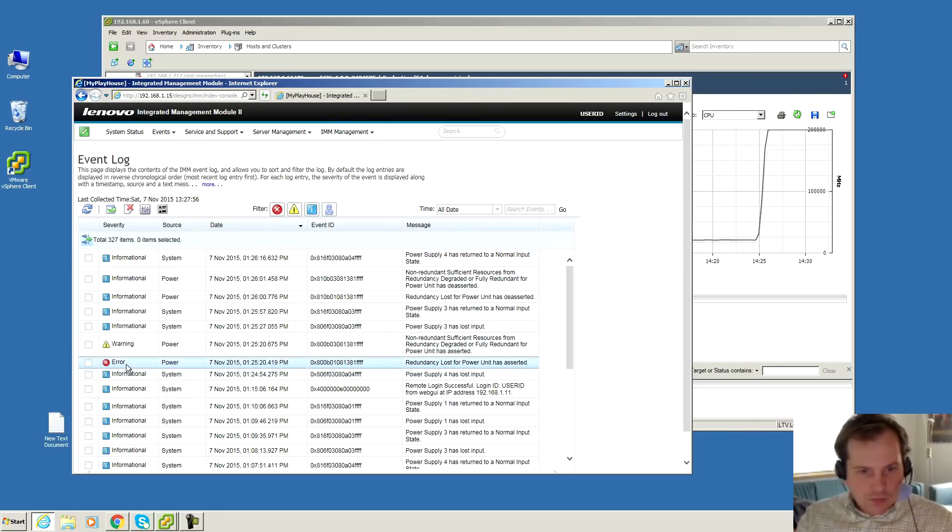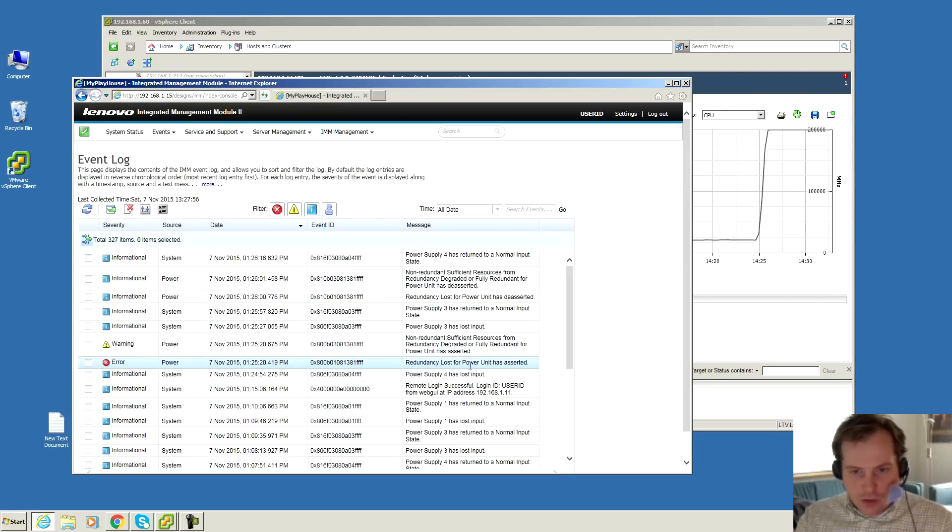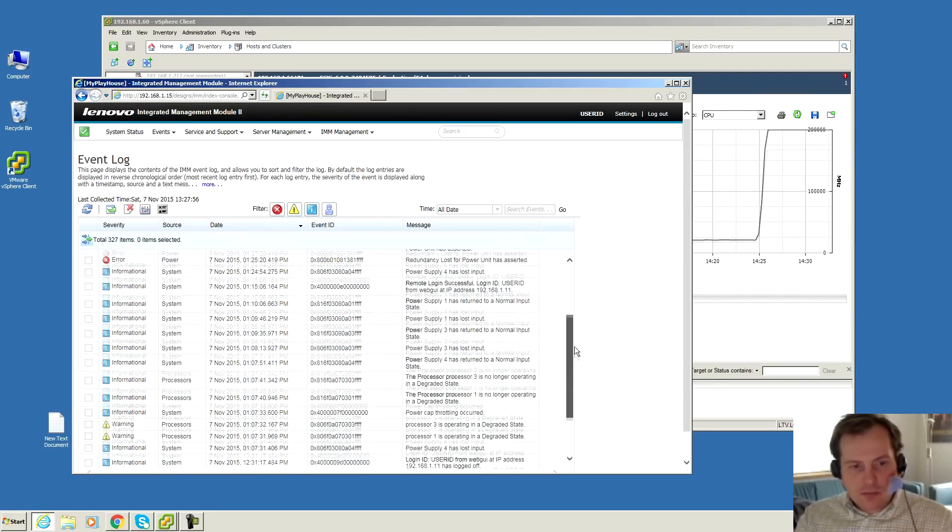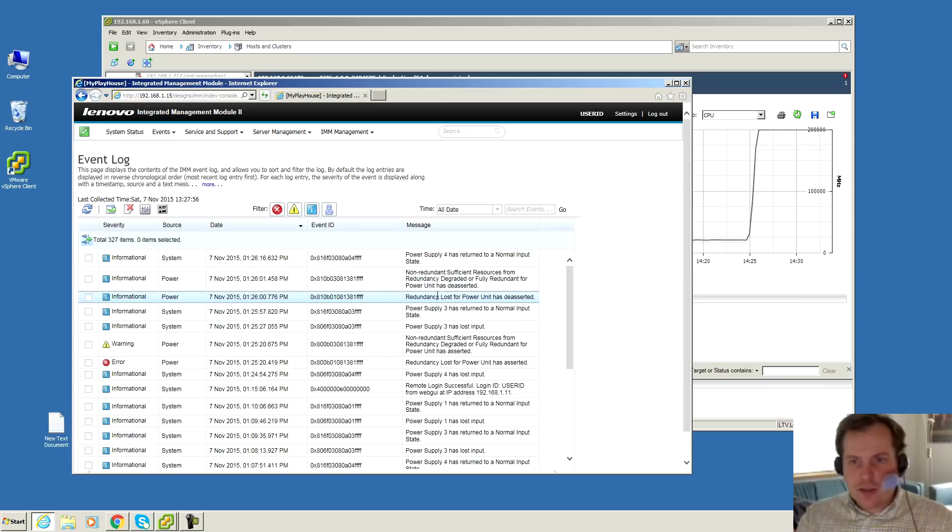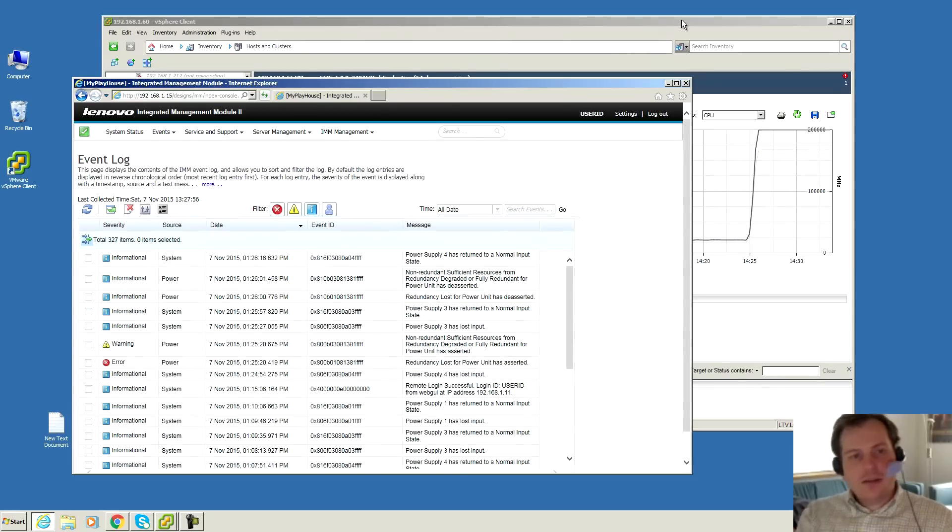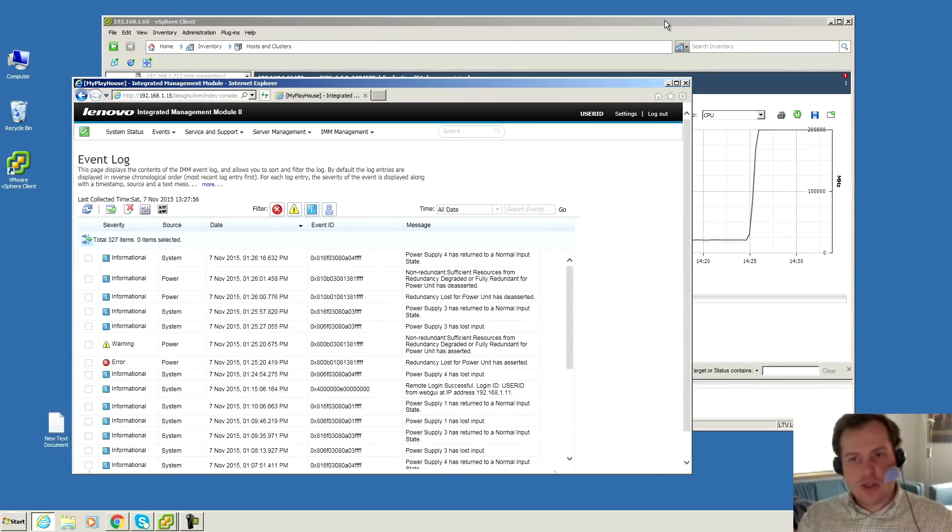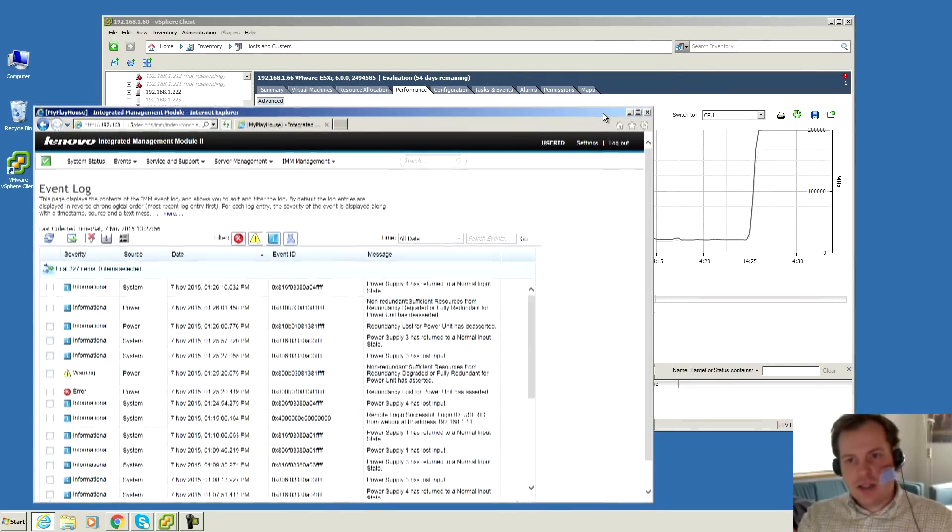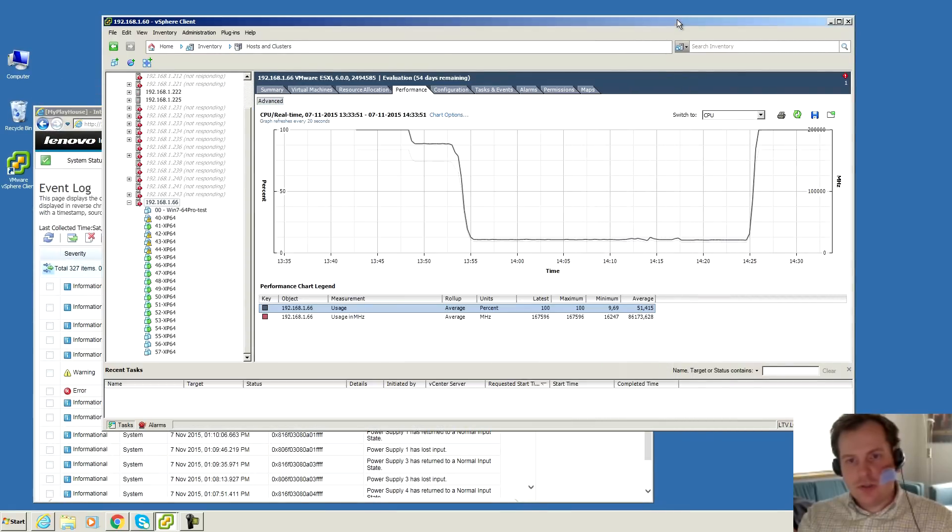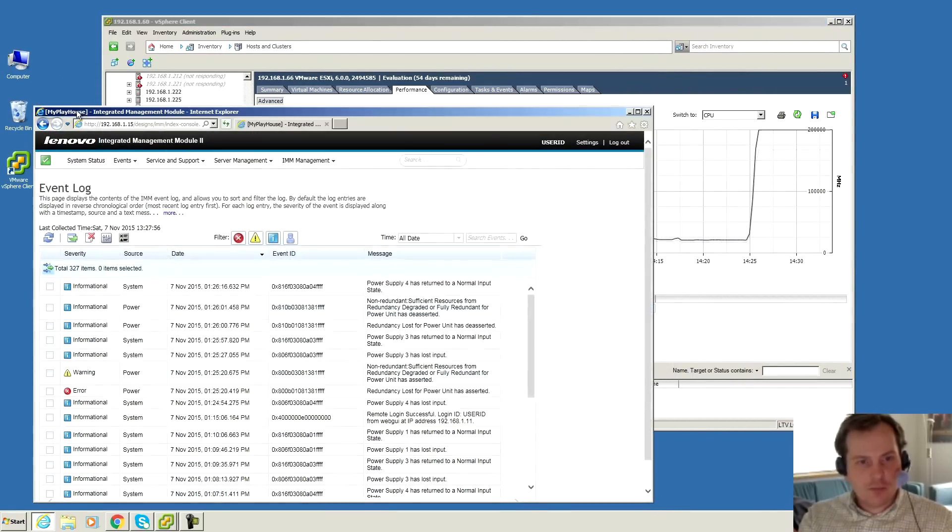Error. That's a tough one. That's redundancy lost for power units. It complains about the missing, but it didn't do anything else about it. So it has no problems with losing two power supplies. There might be an issue if it loses two power supplies in the same...